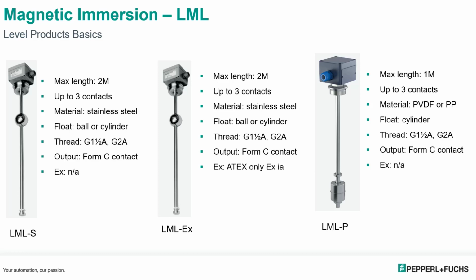The LML-EX is basically the same as the LML-S, except it has a certification on it for ATEX only, for EXIA. And then the LML-P, which is a PVDF or polypropylene, depending on what you want, as a float unit. 3 contacts, max length is 1 meter though, and it is for non-hazardous locations.